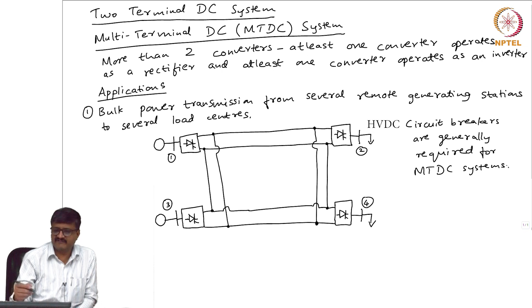Now, if you have only 2 terminal links, can I do away with the circuit breakers? Suppose I don't have multi-terminal, I have just a 2-terminal system, or in this case 4 2-terminal systems. Instead of one MTDC system, I can still have, for the same connection, 4 2-terminal systems. If there is a fault somewhere on the transmission line, can I avoid circuit breakers?